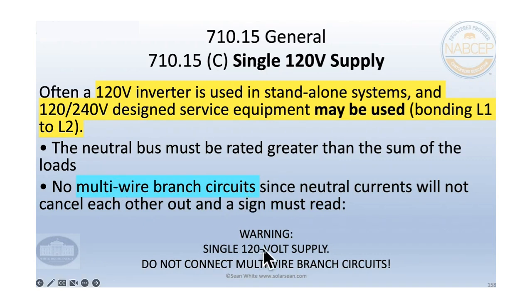So you have to have a sign that says single 120 volt supply, do not connect multi-wire branch circuits. And so that's just if you're using 120/240 equipment for a 120 volt system, which is kind of neat to be able to do. You just can't be using multi-wire branch circuits, which means you would have some Romex or something that has line 1, line 2, neutral, and ground, and then line 1 and line 2, you'd add them together, and that would be how much current would be on the neutral instead of them canceling each other out when you are out of phase.